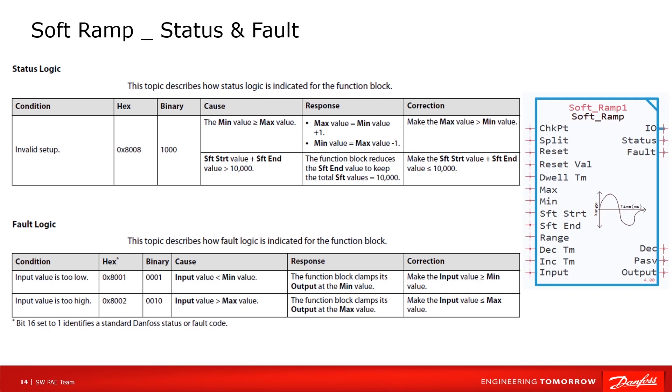There are also output pins of status and fault on this function block. We can read binary data 0x8008 in the status pin when parameter's configuration is incorrect. We can read binary data 0x8001 or 0x8002 when input too low or too high.